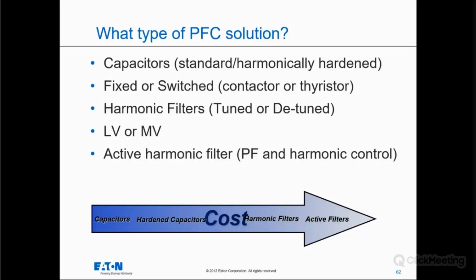So what type of solution do I need? Do I need capacitors? Do I need standard or harmonically hardened because I have a harmonic environment? Do I need fixed or switched capacitors? If you go home at night and turn all of your equipment off, fixed capacitors will put you into a leading situation. So you may need switched capacitors. When you go home, it switches off with the load. As the load goes down, it takes banks of capacitors offline.